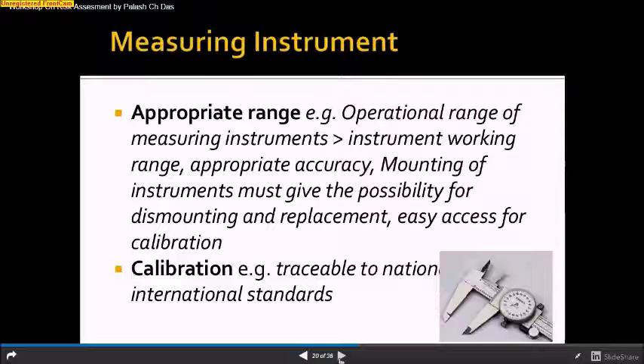Sometimes you have a cold chamber and you have put a sensor in the top of the cold chamber, which is very difficult to dismantle, or calibration is very painful. So you should check whether there is an extra cable lying there, so that you can dismount the sensor and calibrate it. Then the calibration certificate also plays an important role. You should have traceability, you should have a document, because auditors see documents, not the efforts that you are putting in 24/7. They need documents.